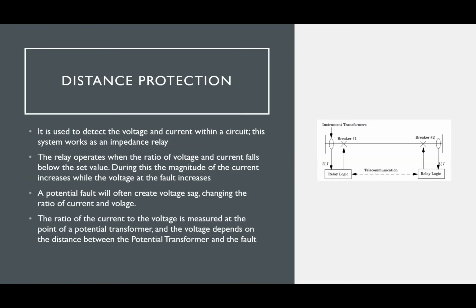This is used to detect the voltage and current within a circuit. This system works as an impedance relay. The relay operates when the ratio of voltage and current falls below the set value. During a fault, the magnitude of the current increases while the voltage at the fault decreases. A potential fault will often create voltage sag, changing the ratio of current and voltage. The ratio of the current to the voltage is measured at the point of a potential transformer, and the voltage depends on the distance between the potential transformer and the fault.